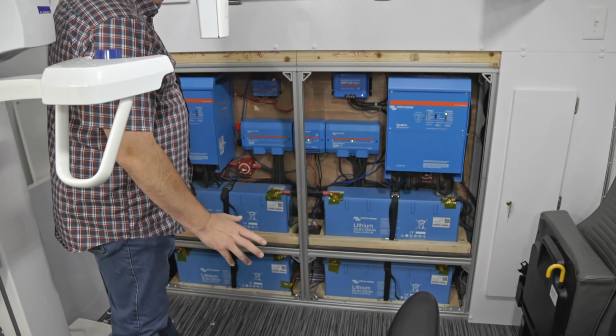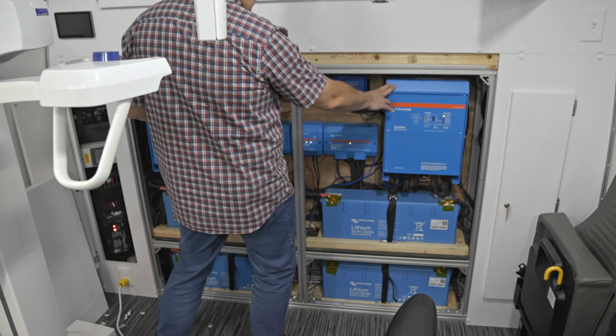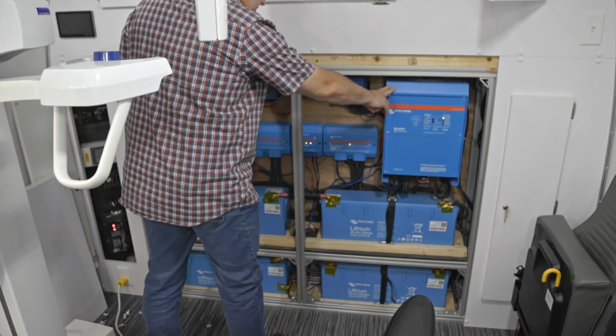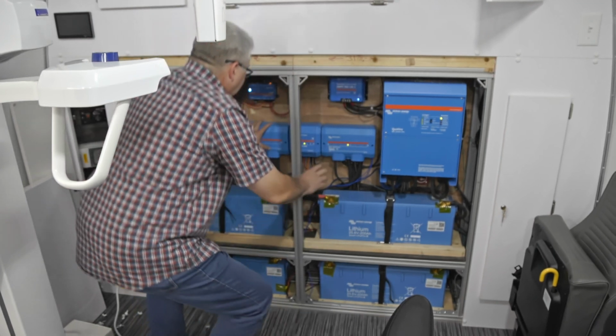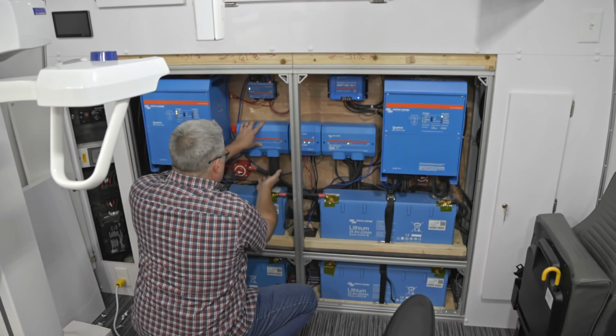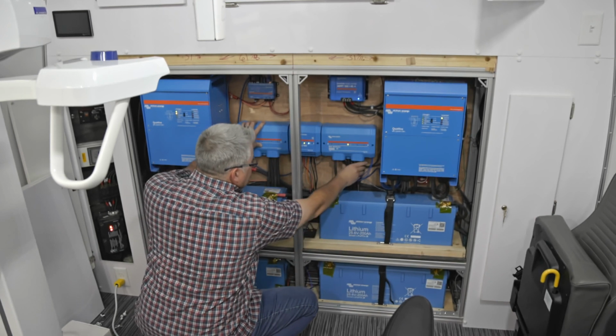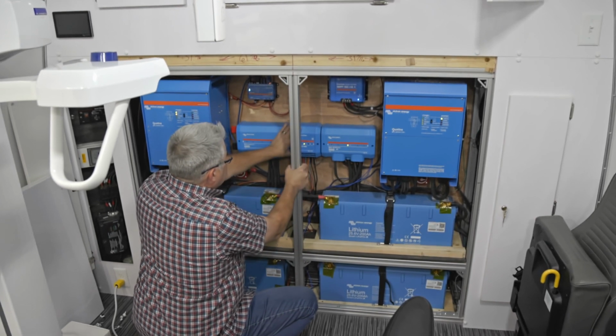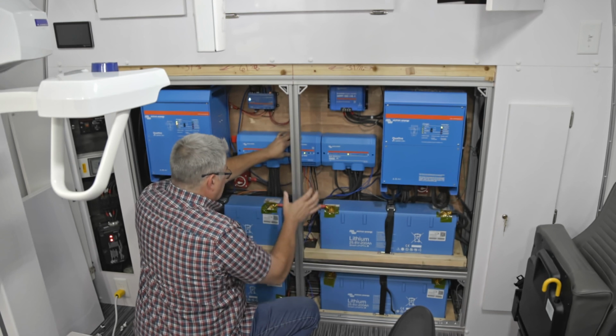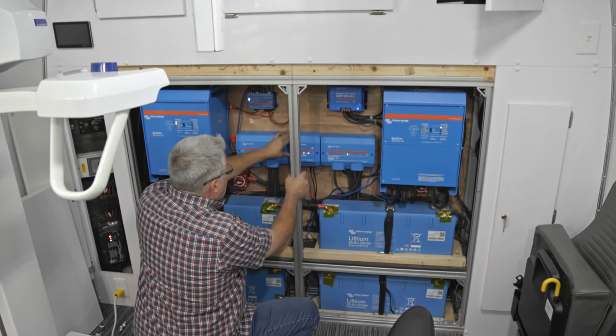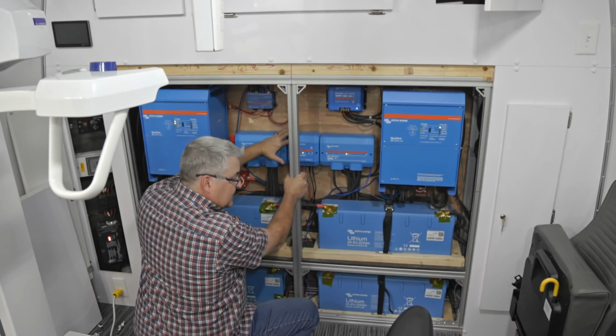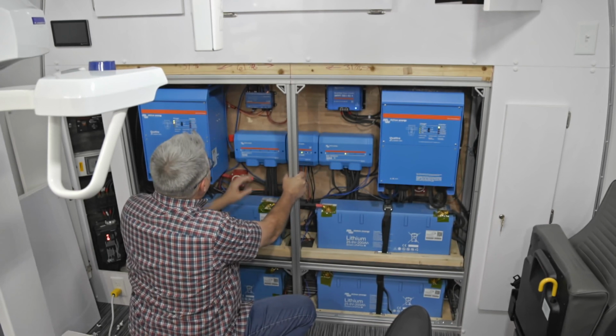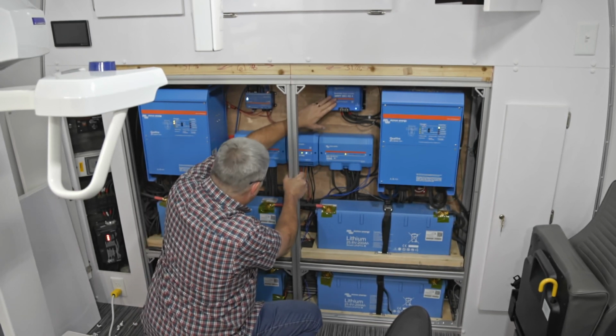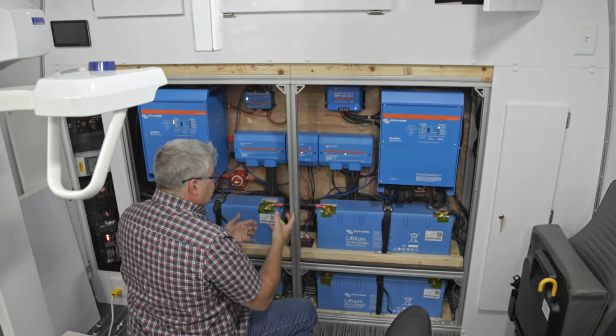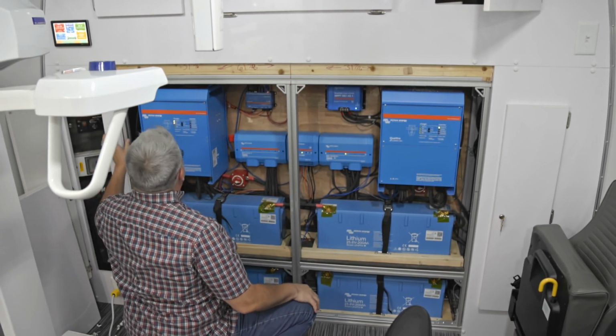So the main components of the system are the inverters, which operate as a single inverter. We've got the DC bus bar system, where the batteries come in one side, and all the loads and chargers are on the other. The BMS is in the middle. The BMS monitors the state of the batteries, and if necessary, will disconnect the batteries from the rest of the system. The servo, the smart solar charge controller. This is the Victron system, and we can see what's going on on the touchscreen.